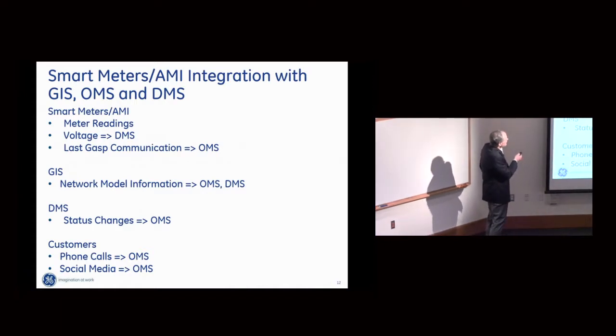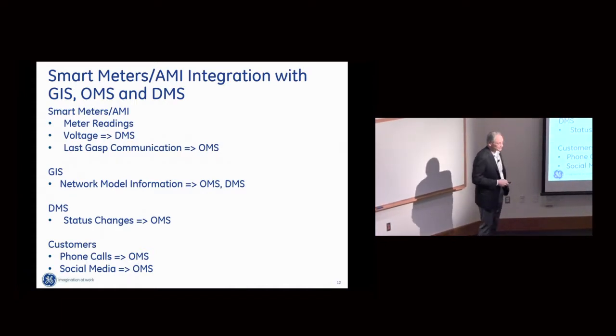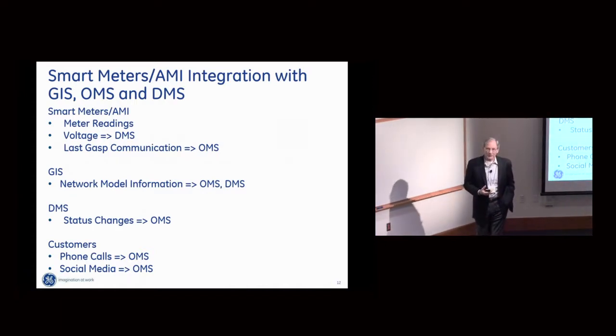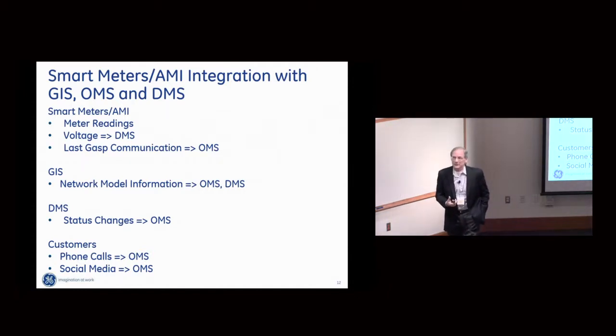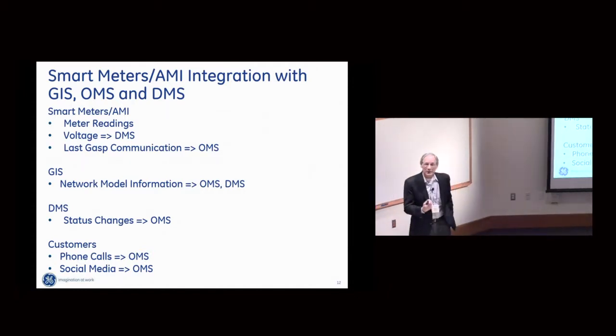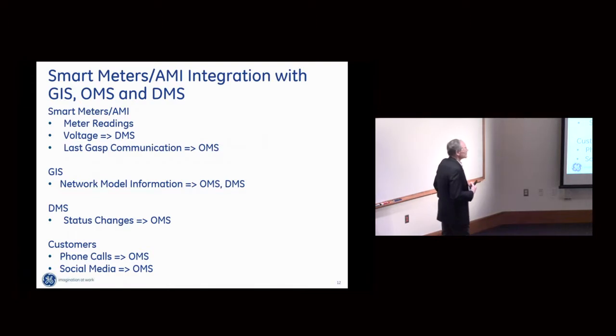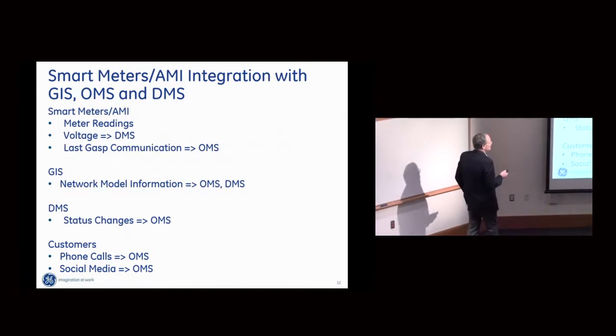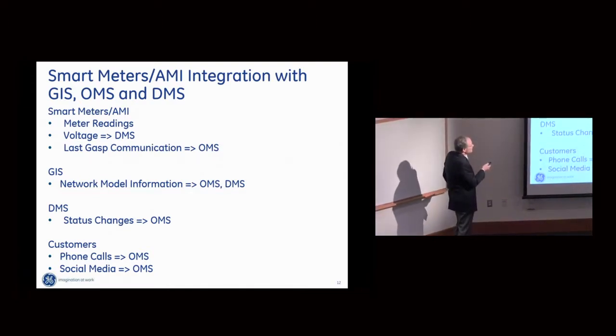Also, the meters give me a 'last gasp' communication—there's a capacitor inside that, when the meter is energized, stores enough energy so that during an outage there's enough for one last transmission. So I know all the customers who had an outage and when it occurred, and I put that right into the outage management system.